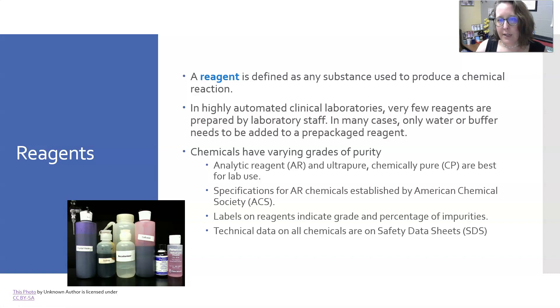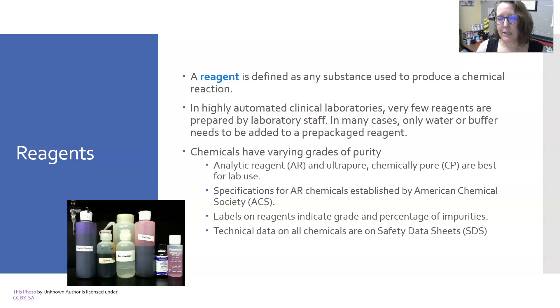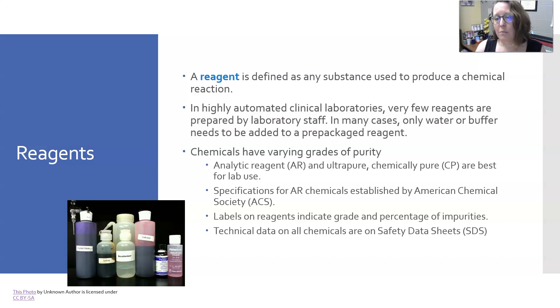A reagent is defined as any substance that's used to produce a chemical reaction. We use a lot of reagents in the lab, especially in chemistry. In highly automated clinical laboratories, very few reagents are prepared by the lab staff — they are purchased from the manufacturers, and they come in kits or reagent packages and are just loaded on the analyzers as is. In many cases, only water or buffer needs to be added to a prepackaged reagent, and even then, most of the time, if water or buffer needs to be added, it's actually done on board the analyzer.